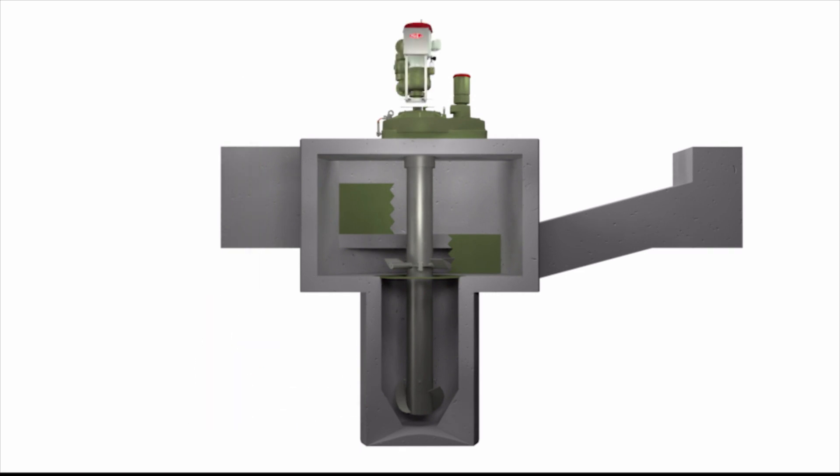The top-mounted Pista Turbo Grit Pump is vacuum-primed. It uses a suction lift pipe that nests inside the drive tube to lift the grit to the dewatering system. The top-mounted pump drops prime between pumping cycles so the grit falls back into the grit hopper. It also uses a flush water system to help keep the grit fluid between pumping cycles.